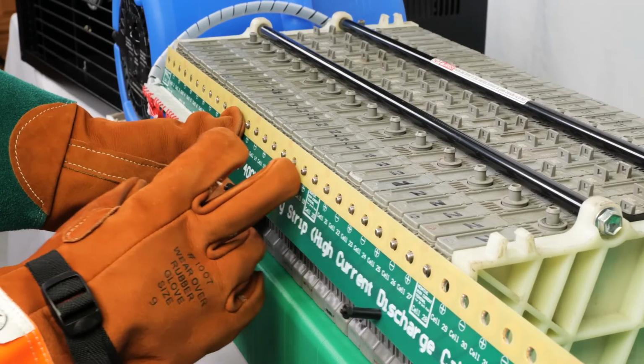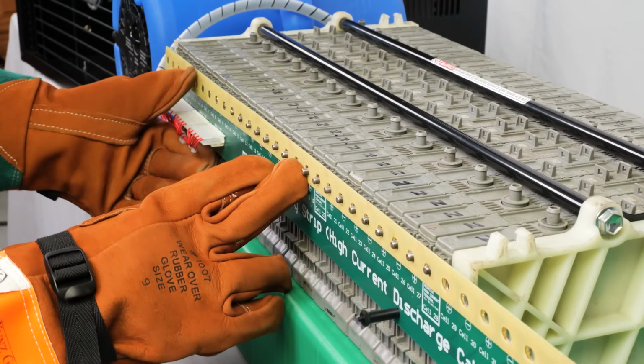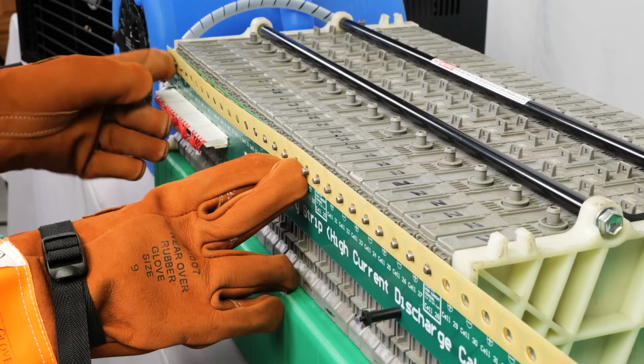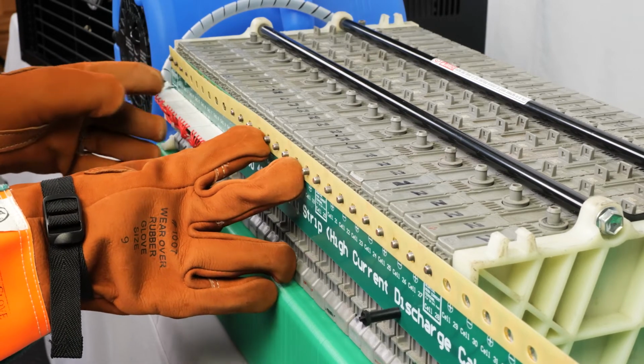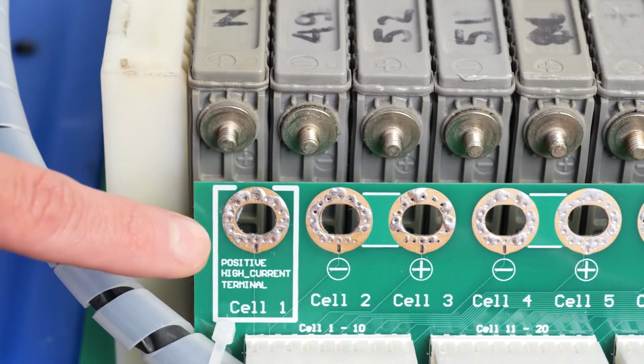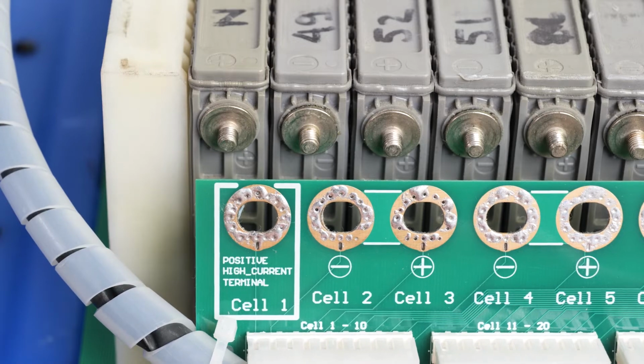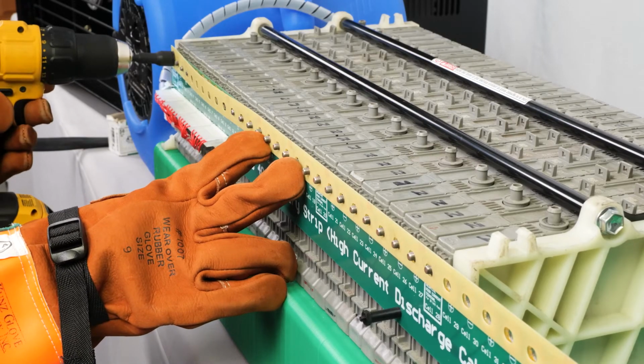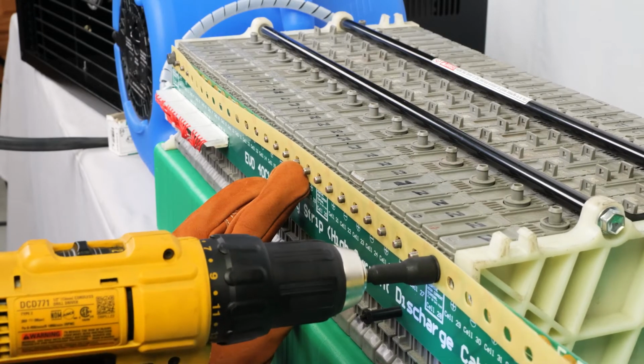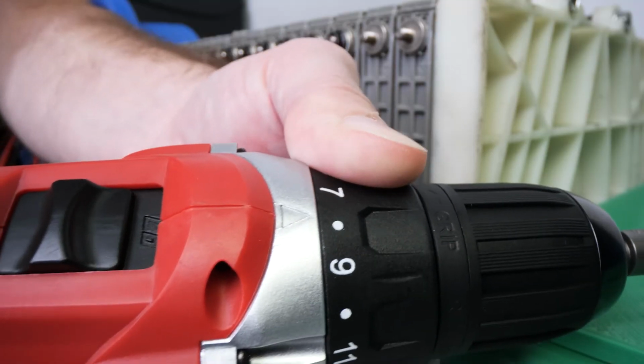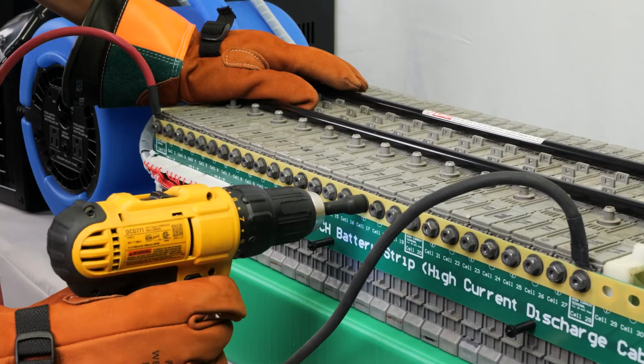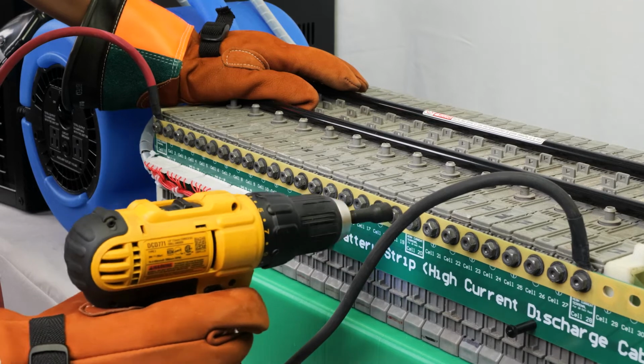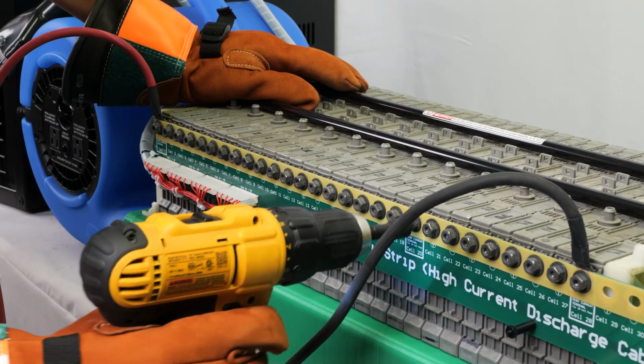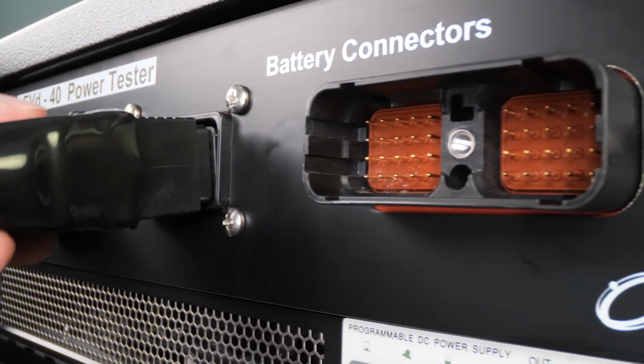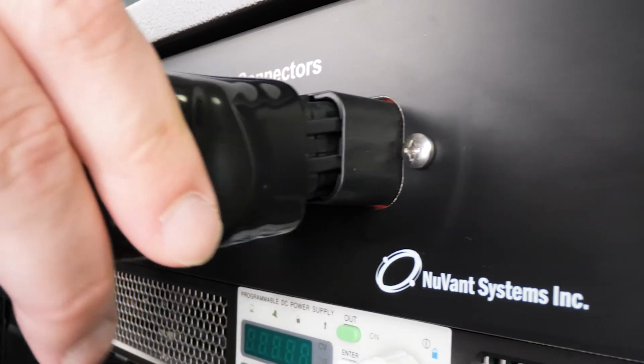We include special spinning washer nuts and insulating strips, which will prevent wear and tear on your harness. We will place the side labeled high current onto the terminals first, fasten nuts onto the ends, and finger tighten the nuts to hold in place. Then use the medium torque setting on your drill to attach the rest of the nuts. Repeat on the other side of the battery pack. At this point, you can plug in the harnesses to the front panel.